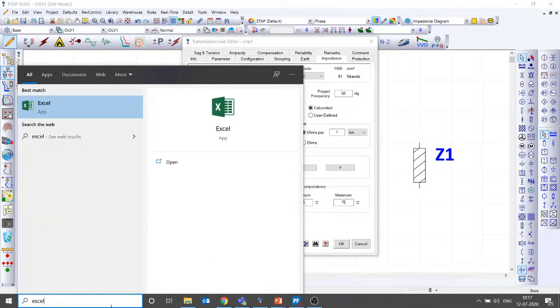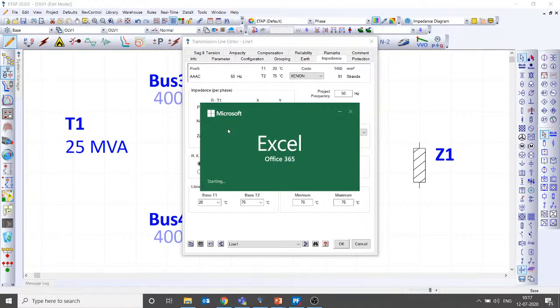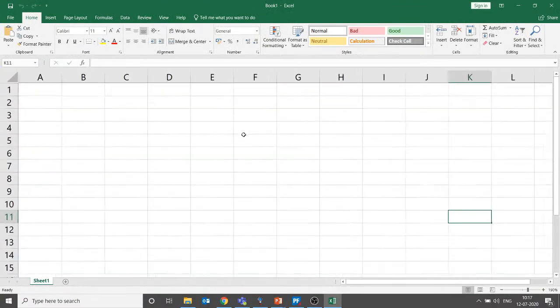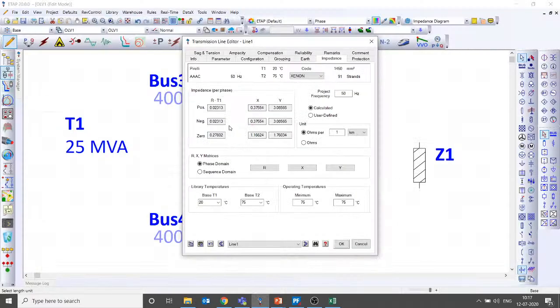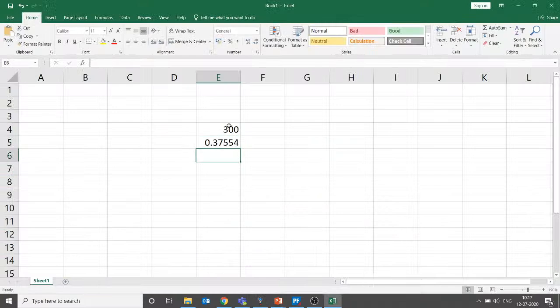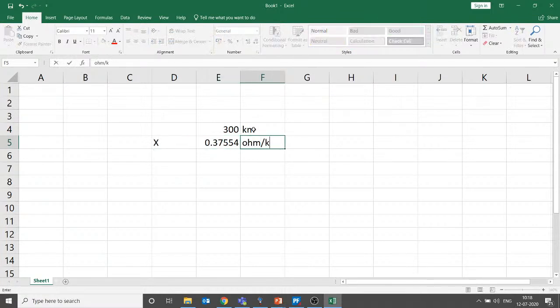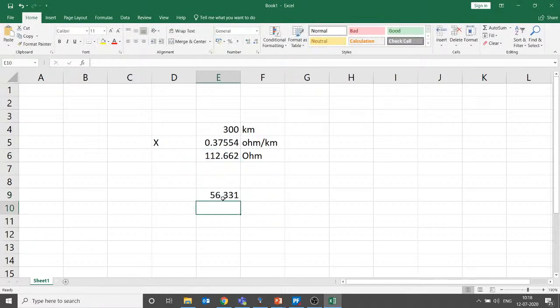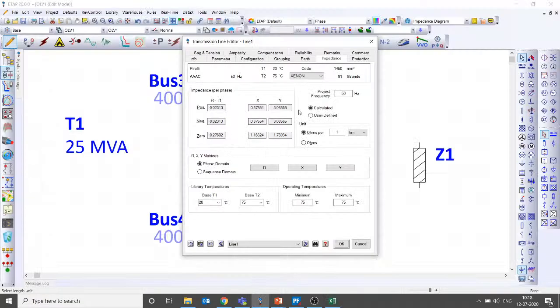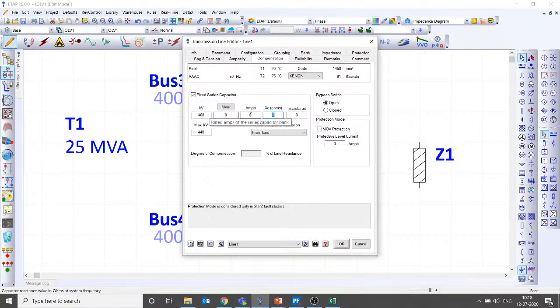So let's assume we are going to compensate this line with the fixed series compensation, and the degree of compensation is 50%. That means 50% of the line reactance is what we are going to model. So 300 is the line length, 300 kilometer, and line reactance value is 0.37554. So this is the length, this is the reactance value in ohms per kilometer. So the total ohms for the entire length, and if you want to compensate 50 percent, then you need to give 56.331 ohms as the XC value, which is going to be connected in series. How to do that? You can add it here directly, that is XC, so you need not even give negative, so 56.331. So which you can really model, right? Right.